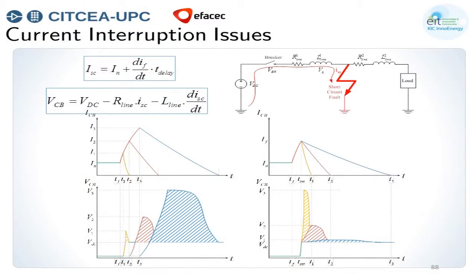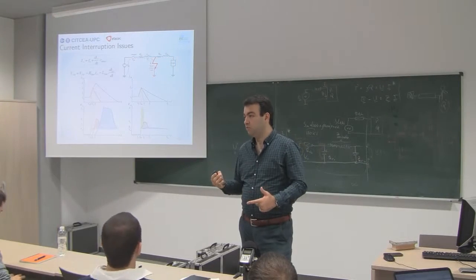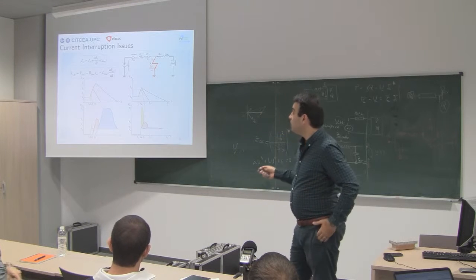Let's see what is one of the main issues regarding breaking and interrupting the current. Because if you have, for instance, solid state switches like IGBTs, you put them in series to be ready to withstand the nominal voltage, and you can interrupt the current. But what is the main issue with that? The main issue is this.